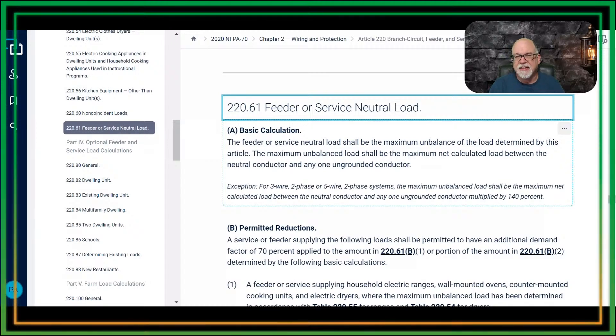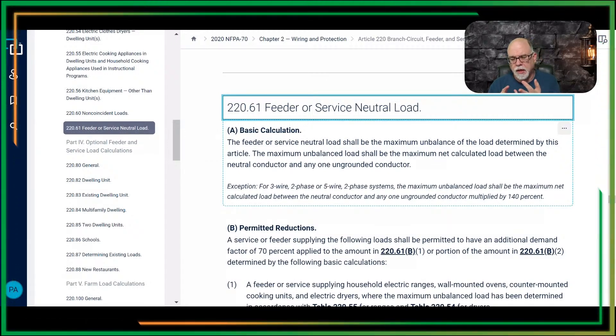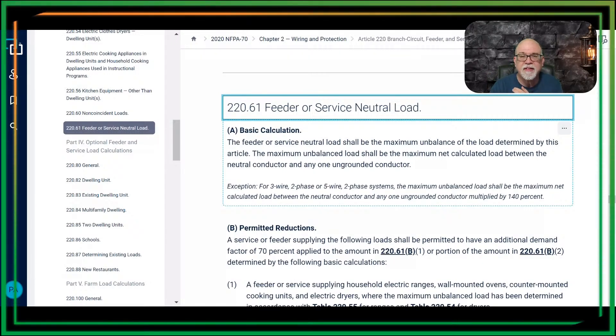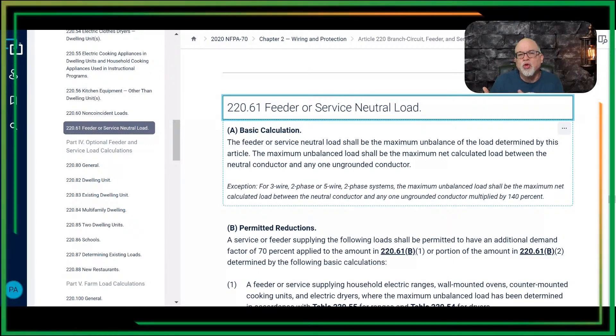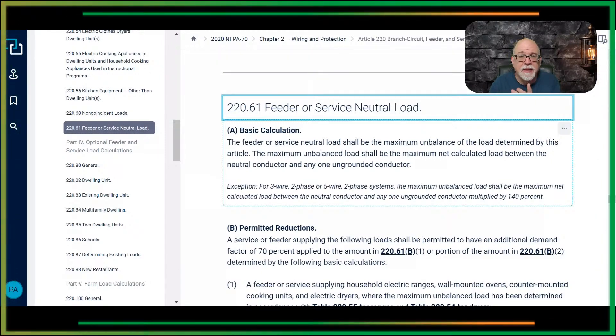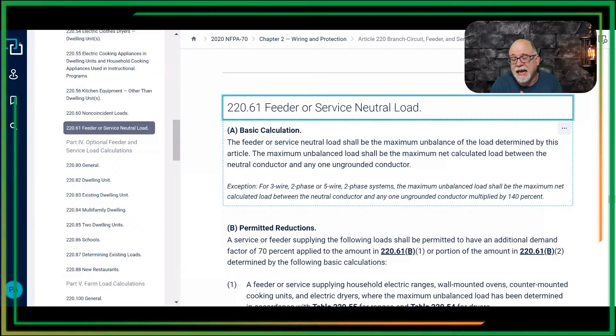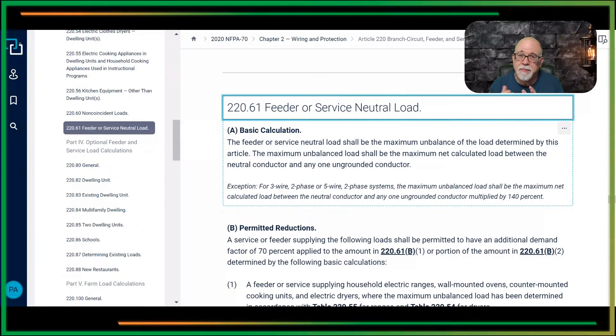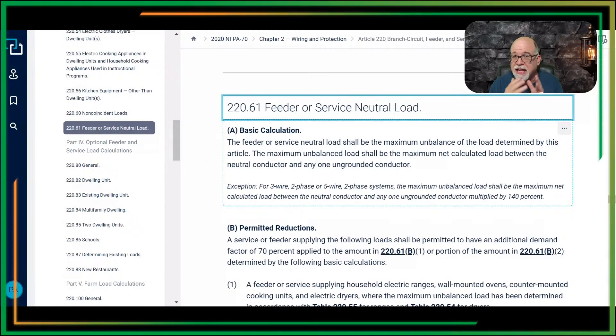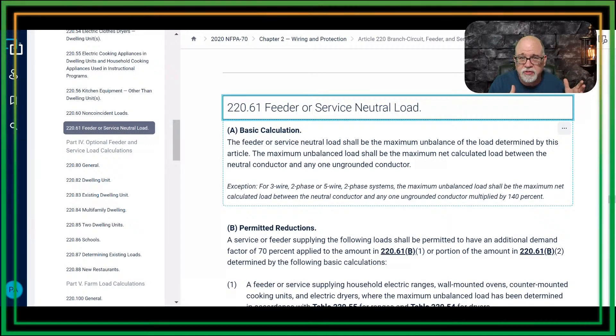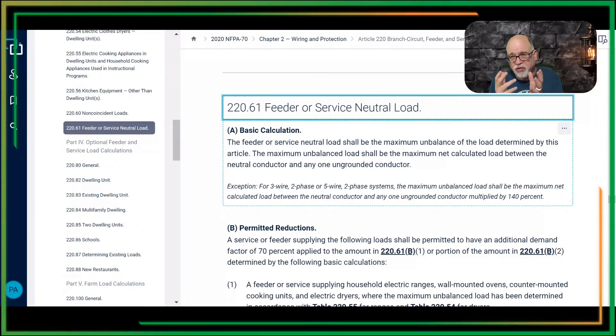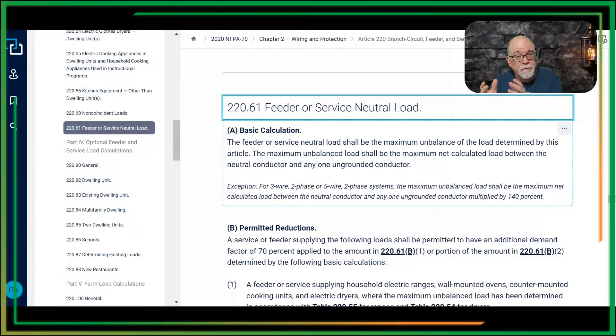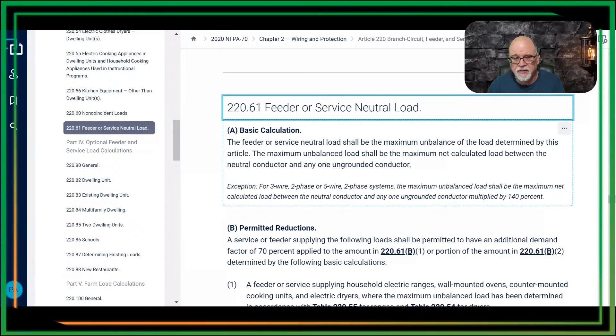But when you get down to things like ranges, cooktops, clothes dryers, counter-mounted cooktops, ovens — things like that — you have a neutral load there, typically for the timers or the electronics. What you have now is the ability to apply a 70% demand factor to those loads that you calculate for sizing the ungrounded conductors. Once you establish what the range or the dryer value is, for the neutral you get to apply a 70% demand to that.